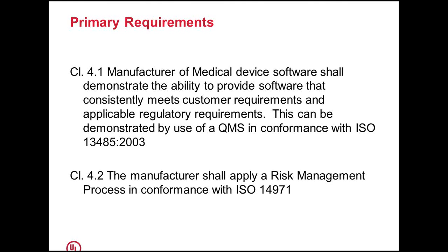This can be demonstrated by use of a quality management system in conformance with ISO 13485:2003. So this gives a direct link of the SDLC process to quality management system requirements. The next requirement in the standard specifies the manufacturer shall apply a risk management process in conformance with ISO 14971.